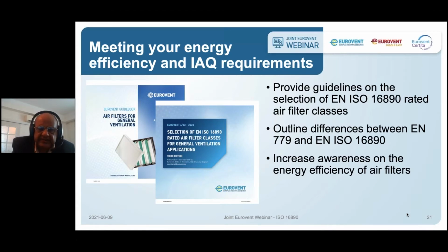Also, there is one point that comes to me time and time again, during such webinars or interviews, we find people asking if offices will go with HEPA filters very soon. Offices are not designed for HEPA filters. The airside systems are not designed for that, and they do impose a lot of external static pressure. Changing systems to get into HEPA is going to happen if push comes to shove, then we'll all have to do it. But basically, that's not the first choice.